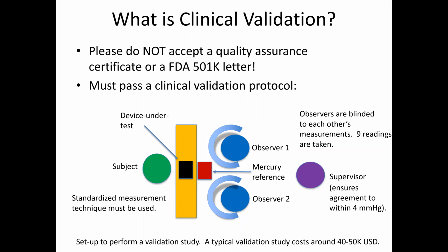Now, what is validation? Because I just told you what calibration was, but I think people may not have a good idea of validation. So we do validation studies in our center, and this is roughly what we would be doing in a closed room that's very quiet. You have the device under test sitting on a table, and the subject across from that. And then you'll have a mercury reference. Sometimes people use 2 mercuries connected with a Y connector, or if it can be easily seen by both observers, just one is fine. And you do blinded measurements, and you take 9 readings, and there's a supervisor that ensures that the observers agree to within 4 millimeters.